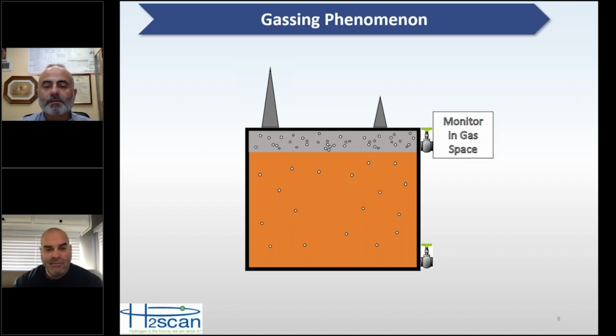One of the things you can do is, and it's actually getting to be more popular today than it used to be, because you used to not have online monitors, and so the primary thing that people did was take an oil sample, send it to a lab, and get their DGA analysis, their dissolved gas analysis. But today you have monitors that can also work in the headspace. There are a lot of different test monitors out there, portables, that can actually pull gas from the headspace and analyze it and give you a total combustible gas, or potentially even just hydrogen if you're interested in that. So gas monitoring in the headspace is actually becoming more and more popular today.